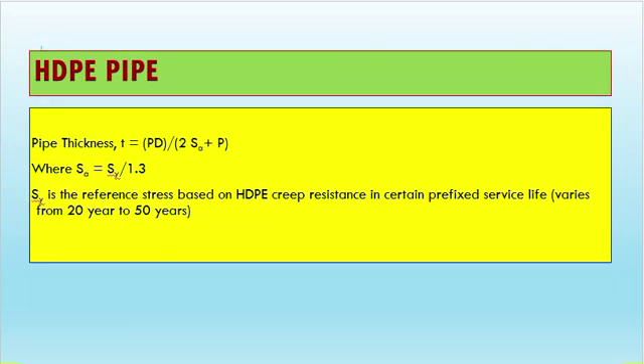For HDPE pipe, the pipe thickness formula is: T = PD / (2 × SA + P), where SA equals SY divided by 1.3. SY is the design stress based on HDPE creep resistance, with a service life that varies from 20 to 50 years.